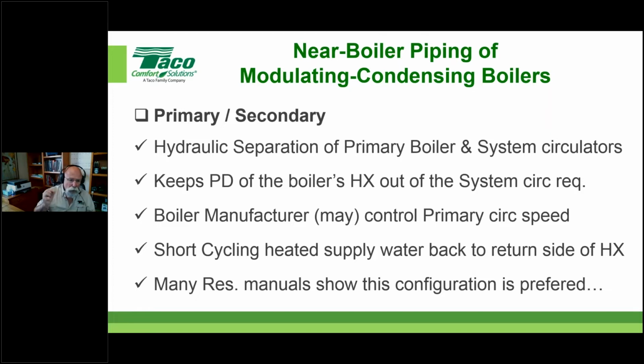One thing I will throw out with this in mind: if the boiler manufacturer allows you to pipe the boiler in series, that means not primary-secondary. Some people call it direct flow or variable primary, or there are some other terms out there. If they allow you to do that and your system affords you that opportunity, then by all means, do it. Then some of these things that we're talking about in primary-secondary don't need to even be considered at that point in time. But there are some caveats to that. So that's why I say just follow the boiler manufacturer's manual, and you'll be safe, okay?